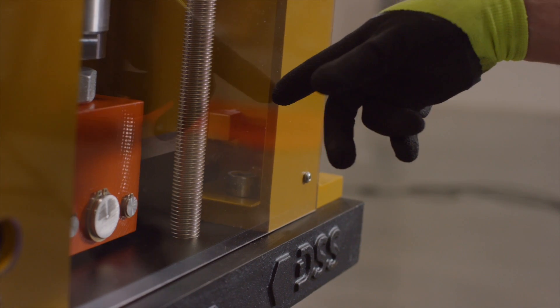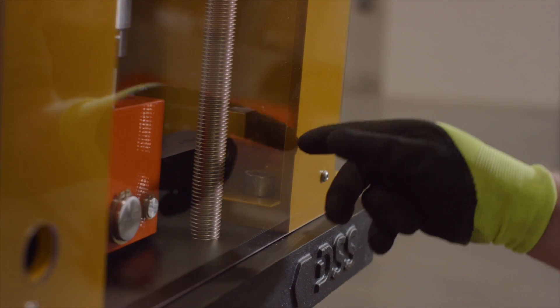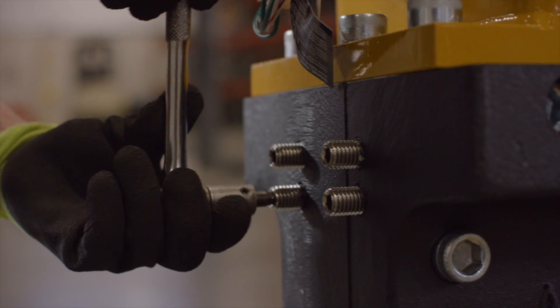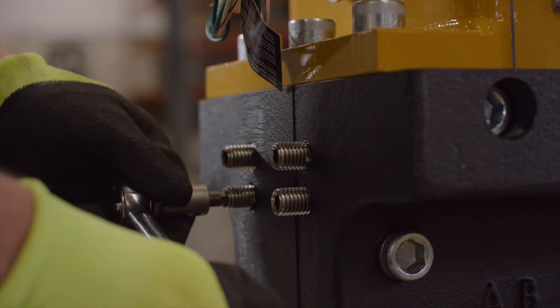It is common for the valve packing to settle in shipping. If you notice a leak during line testing, simply adjust the packing screws. Turn each screw a half turn and repeat until the leak stops.